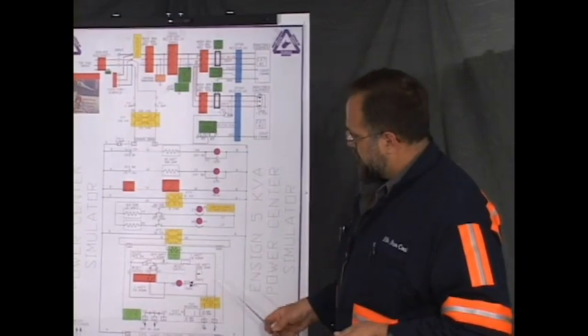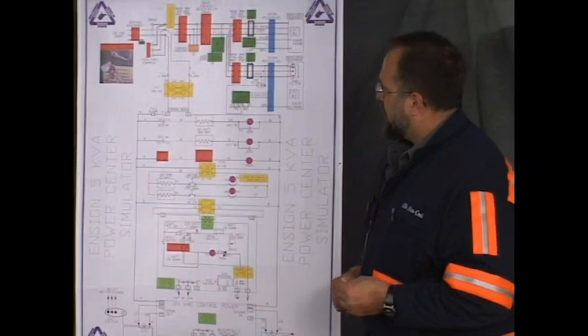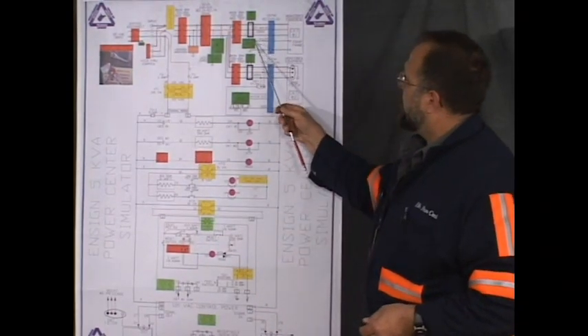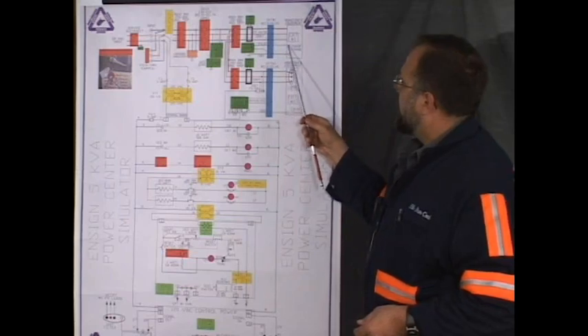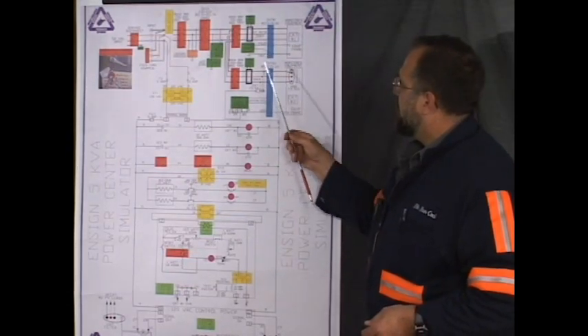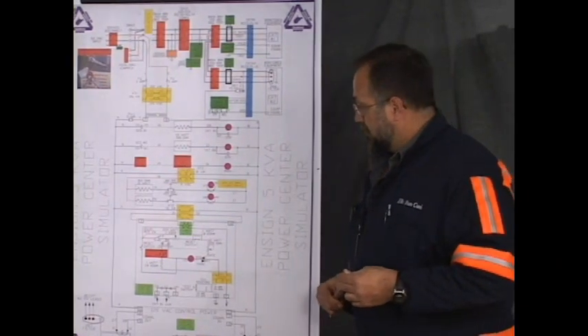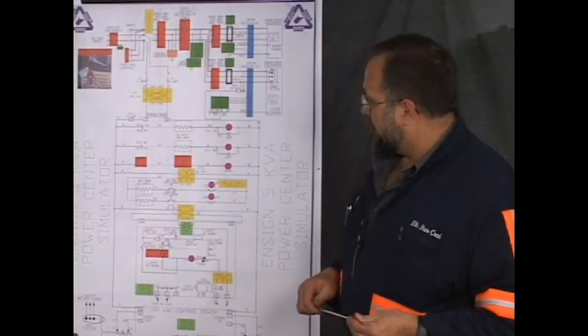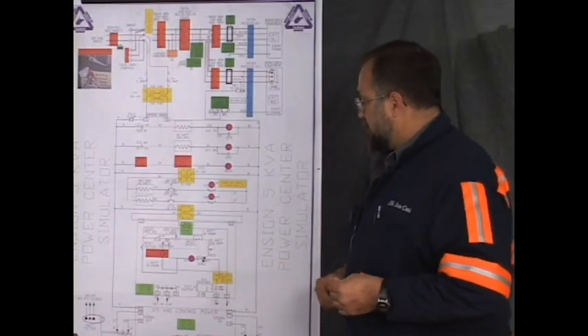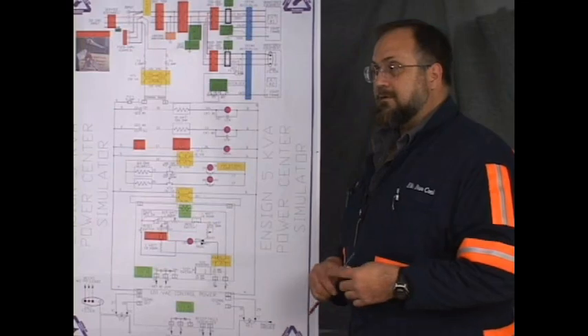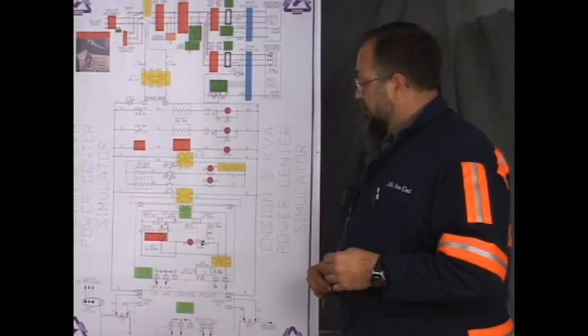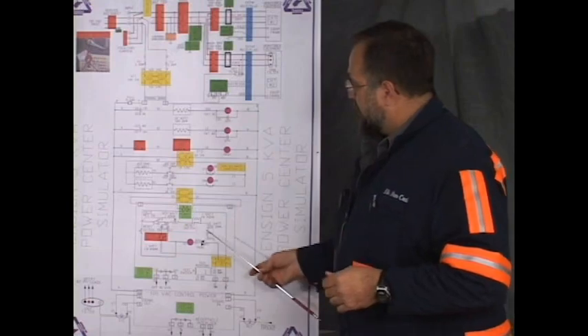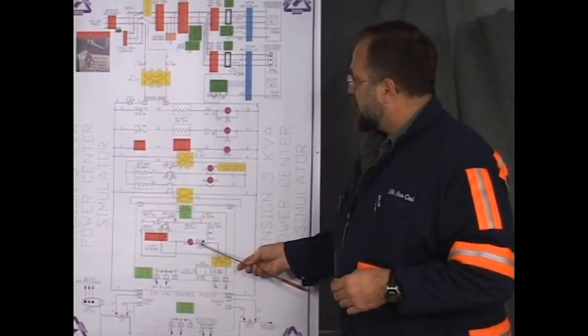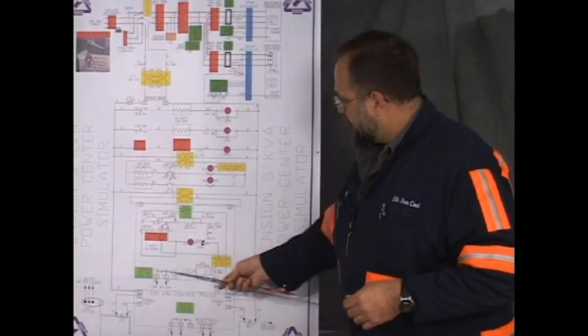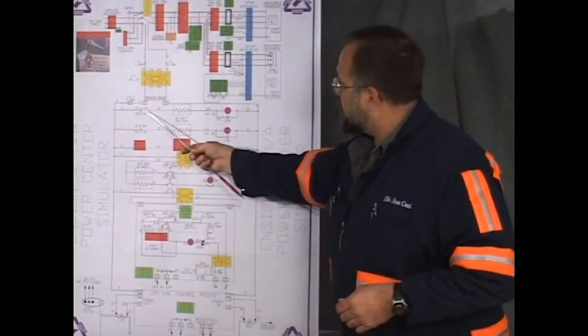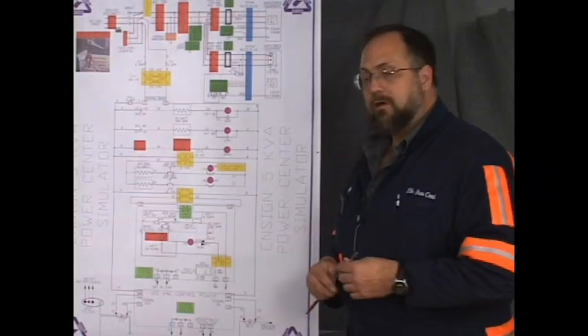Now, before this monitor can be satisfied and close these contacts, it must have a loop from the pilot pin in the cat head to the equipment frame and back, or vice versa. It has to be a circuit. All of these impedance monitors work on basically the same principle. They'll put a small reference voltage on the ground and pilot to the machine and back, and if that circuit is met, then it'll pull a relay in and close a set of tips. This is the coil that has to close, and these are the tips that have to make. These tips are the same as these tips, just drawn in a different spot on the map here.